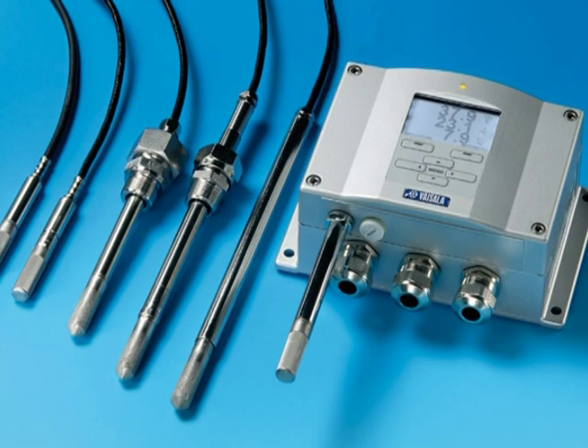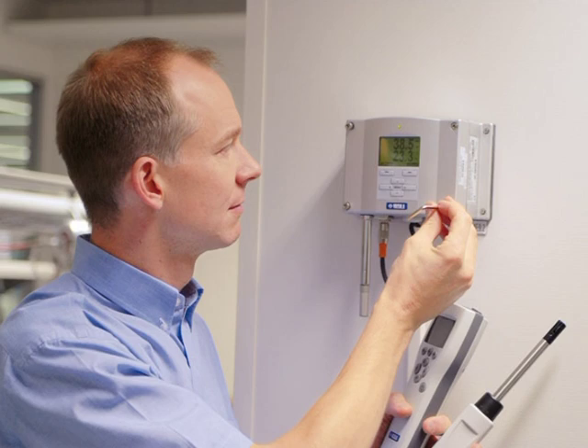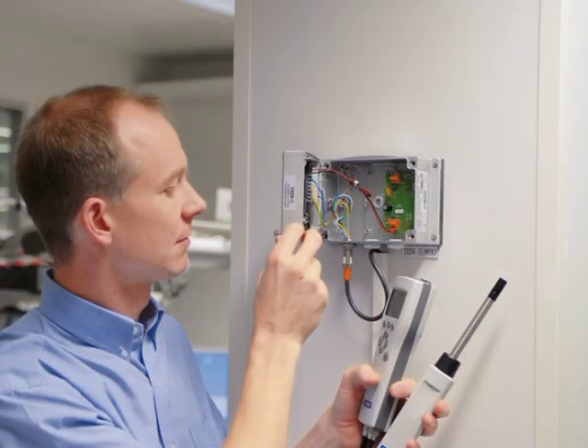All humidity measurement transmitters will drift over time. It's just a question of how much and how quickly. In order to determine whether or not the instrument is still within specification, a reference standard is required.